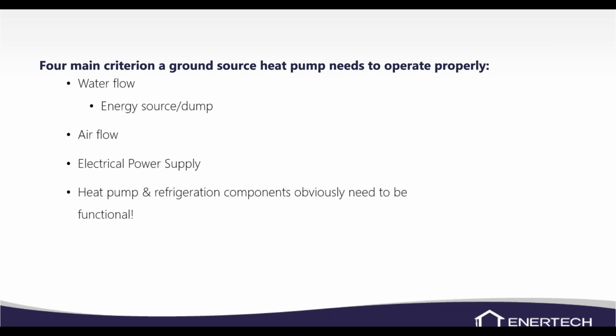Obviously, we need the compressor to be operational, the blower motor, anything inside the unit, contactor, reversing valve. All those components need to be functioning. If one of those is not functioning, we really can't expect the unit to operate properly. So make sure that we've got a compressor that's running, and it will run in first or second stage. If it's a two-stage unit, we normally will check running numbers when it's in second stage. So make sure it will upstage. Make sure your fan motor switches speeds up to Y2 if you're in Y2. So just make sure all the components are operating when you go to diagnose the unit.